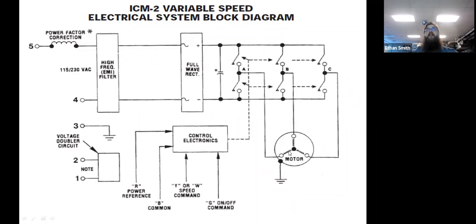So we're pulsing each winding in time with the others so that we're exactly 33% out of phase with all of the other windings so that we get that rotation. The cool thing with a frequency drive or a variable speed control like this is it can actually sense that the motor is spinning by the back EMF that it sees between cycles. And so what you'll sometimes see these motors do when they start up is they'll actually rock back and forth to find their location and then start. So sometimes you'll hear people say this motor growled at me and then started. That's what that's doing. It's finding its rotational location before it starts firing those relays.